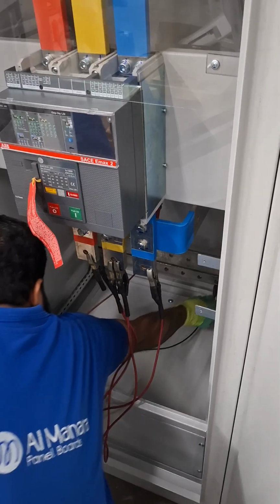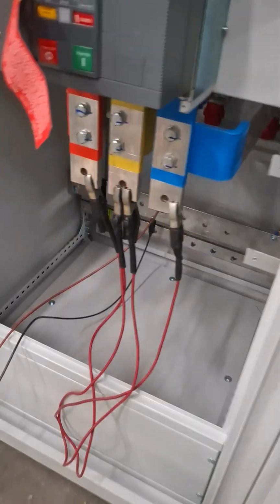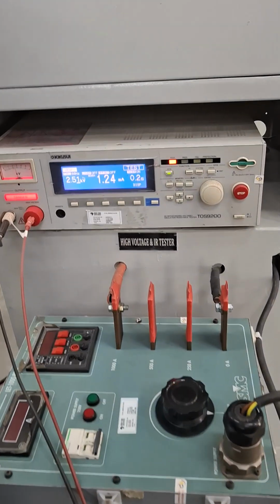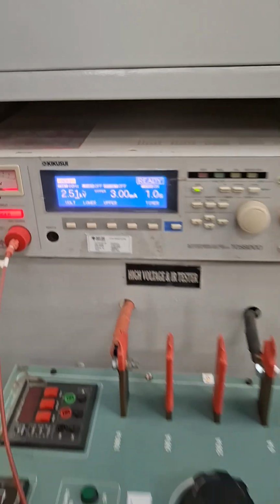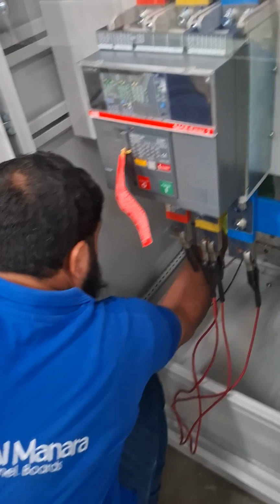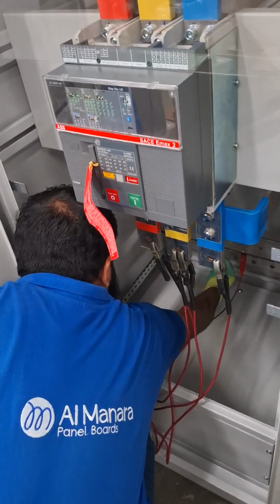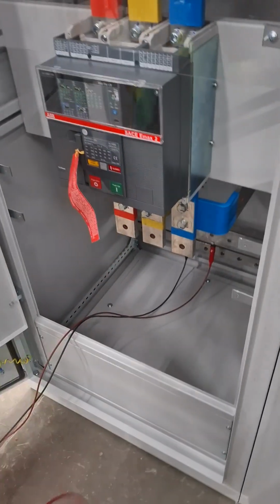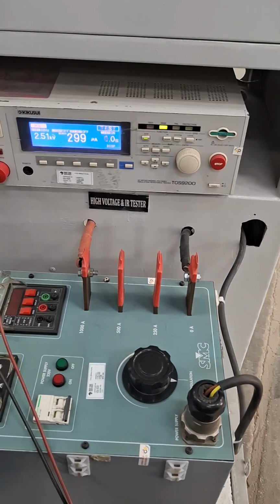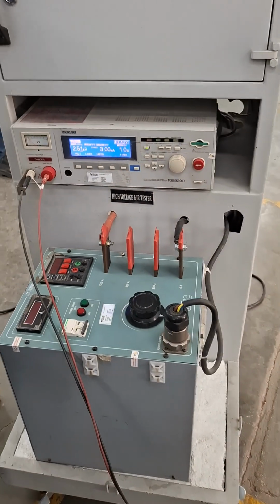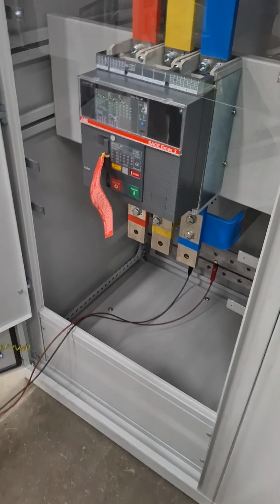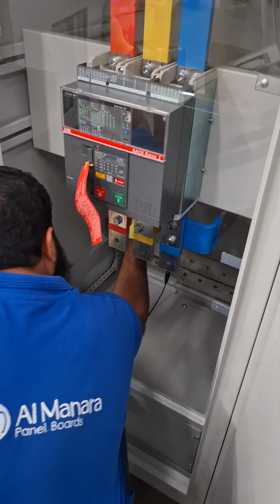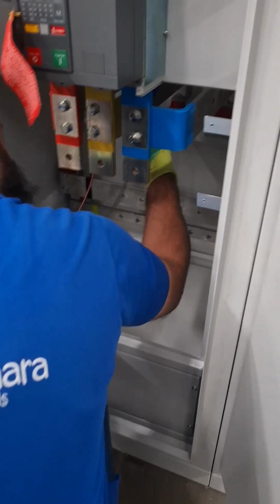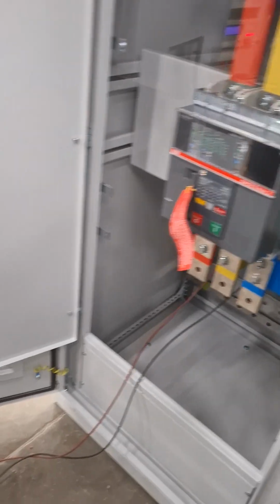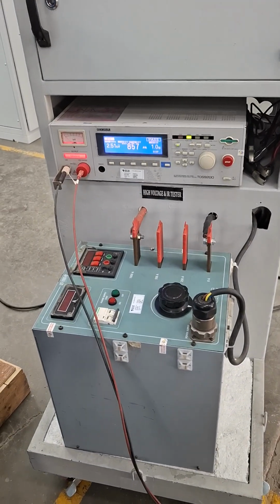Okay, now we applied all phases with neutral. Okay. This is also passed, 1.2 milliampere. This is the leakage current, same here, between phase to phase, phase to neutral, phase to ground. Okay, start. Neutral with ground also passes. Okay. Now we apply phase 1 with phase 2. Also pass.